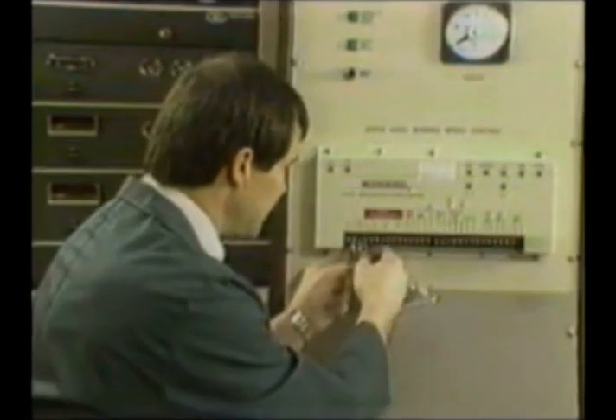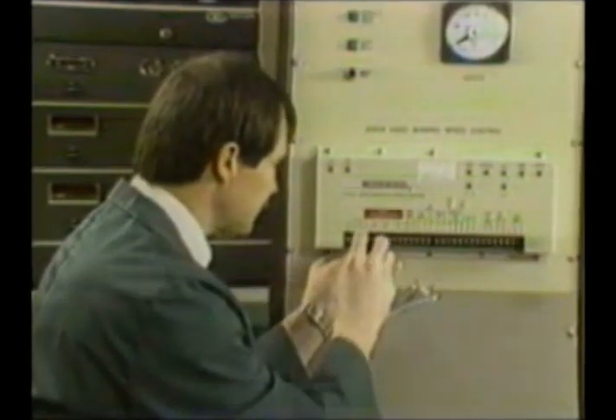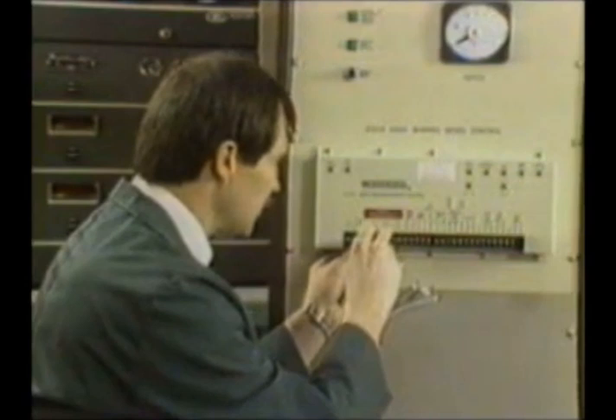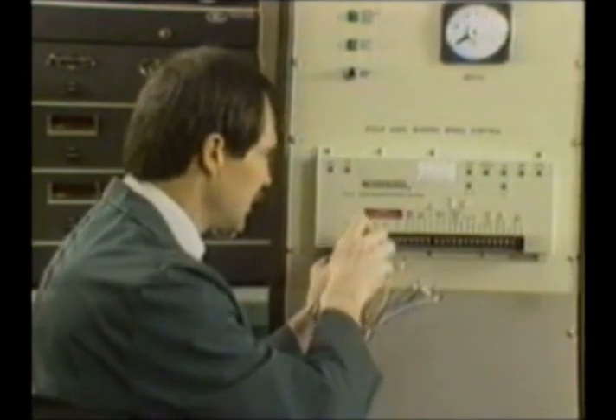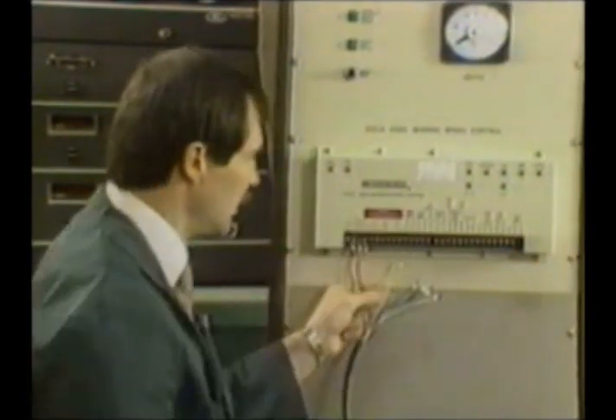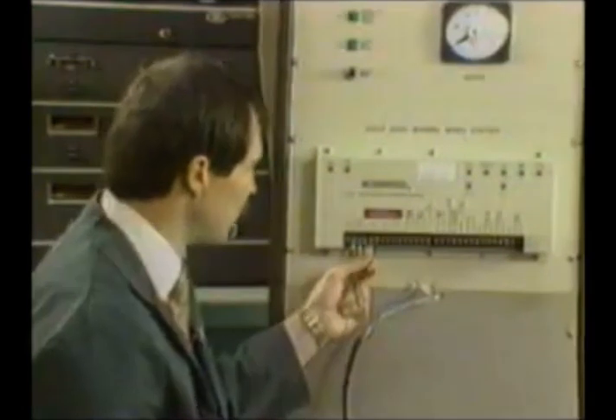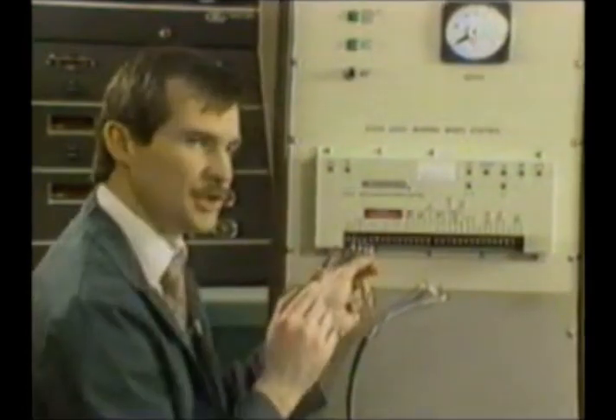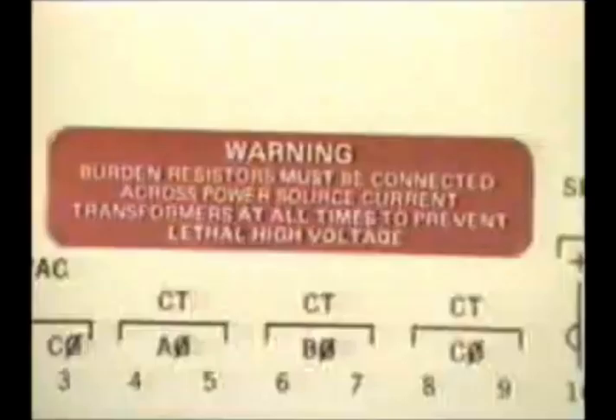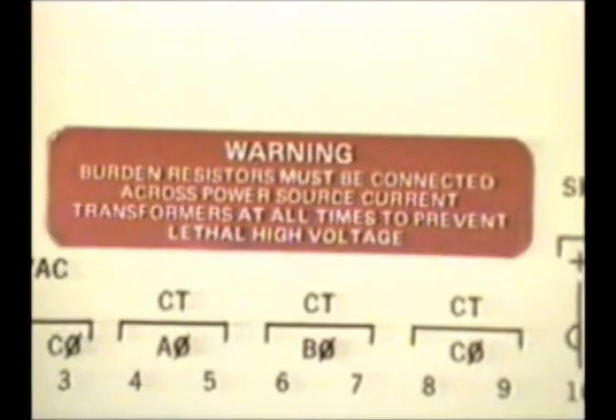Once we have the potential transformers hooked up, we'll go to the current transformers. The current transformers now, we do not provide burden resistors in our control anymore. The burden in our control is really a dead short. We use a current transformer, which we jumper a 16-gauge wire through to measure the current through the CTs. That gives us better isolation than in the past.